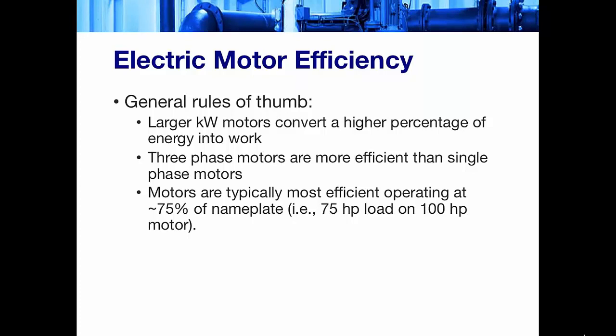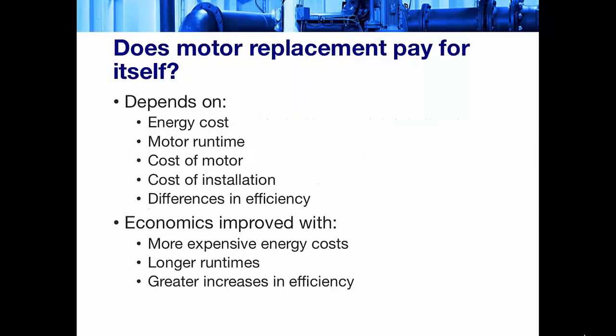On the question of whether the motor replacement will pay for itself, on the next slide, the answer is it really depends. What does your energy cost? How many hours a day does this motor run? What is the cost of a new motor and the installation? And then what's the relative difference in efficiency between the motors? The economic case is going to be improved as you have more expensive energy costs, longer run times, and greater differences in efficiency between the two motors. So on a case-by-case basis, you'll have to do the math, taking these things into account.